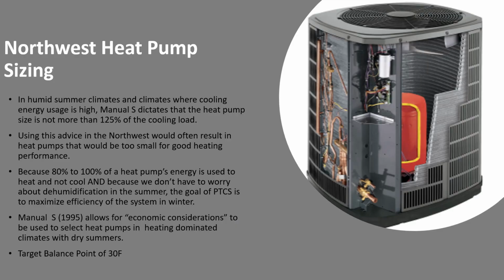Northwest heat pump sizing, boy, we kind of get a break. We don't have humid climates. So if we oversize technically a little bit on the cooling side, we're not going to have too many comfort complaints due to high indoor humidity. The good news is that in the Northwest, most of the time we have a heating dominated climate and not a cooling dominated climate, and it makes more sense to design for winter performance than it does summer performance.